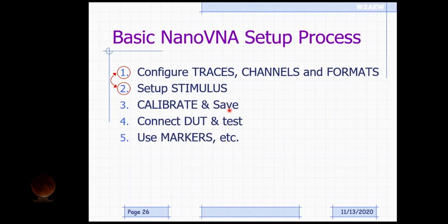I can add markers, extract some numbers off, things like that. And then if you want to adjust the traces and formats, you can add traces, take them away, things like that. That's all fine. If you change the frequency that you're measuring, then you probably want to recalibrate again. But just changing which traces are turned on or off and what channels they're on, you don't have to rerun a calibration, only really if you change the stimulus or the frequency range.